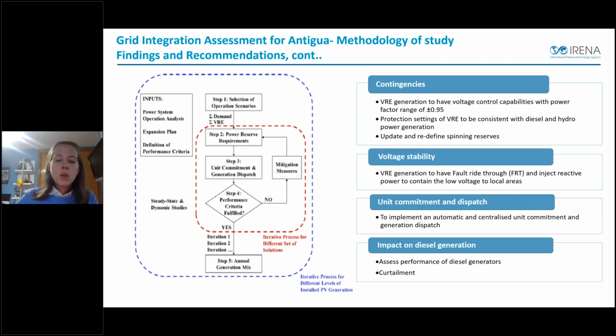As an example, we can see the analysis provided in the case of Antigua, where an increased risk of voltage and frequency deviation was experienced. As Mr. Matias said, it was recommended that variable renewable generation should have power factor capabilities of plus/minus 0.95. Protection settings were to be modified according to the working of the other generators, and spinning reserve updated and redefined to match the loss of the largest generator. PV generation was required to have fault ride-through capability to contain voltage levels locally, and also keep frequency deviation to a minimum. An automatic and centralized unit commitment and generation dispatch were recommended.